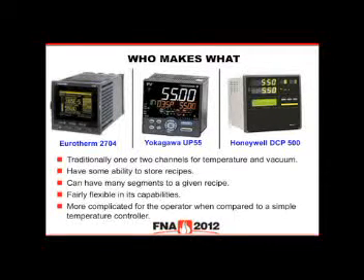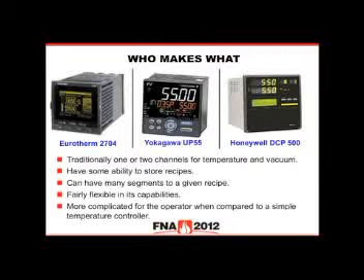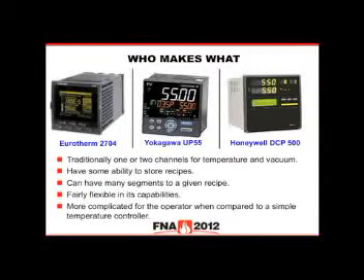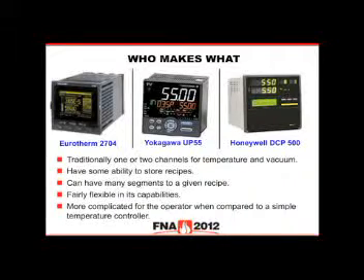The Honeywell DCP 550 and 551 are still available — they've been around about 15 years, a good simple product. Eurotherm makes a model 2704 and also a simpler 3500, but the 2704 is similar to the 551 and also to Yokogawa's UP55. These have one or two channels — typically just one unless you're trying to have some type of pressure control loop tracking temperature. They've got recipe storage and are typically segment-based, so you can have long complicated heat treat cycles.